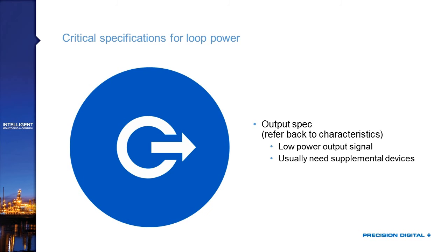The difference is that a relay is going to be able to support high AC voltages, and it's going to have 3 or 10 amps that it can afford to run through it. My open collector output may be limited to the milliamp range and a couple of volts. And that's going to greatly change how I wire my system, because now I need to use my open collector output to run some kind of solid-state relay that then controls a device, as opposed to just being able to run the power right through my relay.